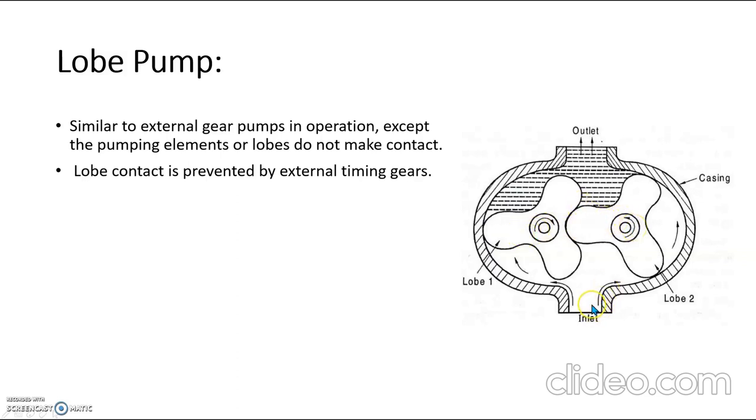As we can see in the external gear pump, there is inlet and outlet. The major difference in the lobe pump is there is no contact between these two. This contact is prevented by external timing gears, and the shaft of the lobe pump is driven independently.